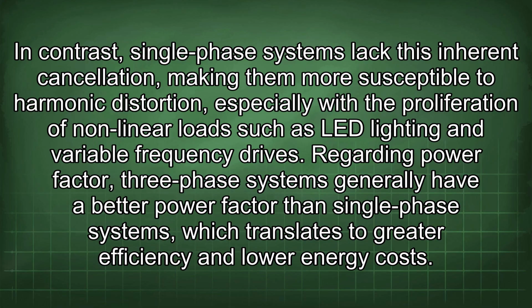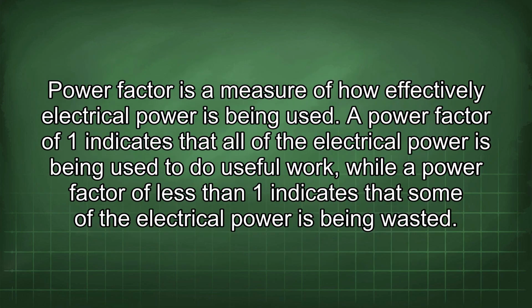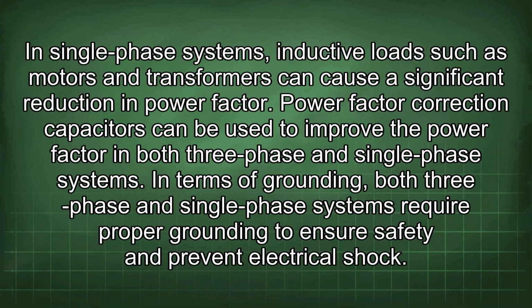Regarding power factor, three-phase systems generally have a better power factor than single-phase systems, which translates to greater efficiency and lower energy costs. Power factor is a measure of how effectively electrical power is being used. A power factor of 1 indicates that all of the electrical power is being used to do useful work, while a power factor of less than 1 indicates that some of the electrical power is being wasted. In single-phase systems, inductive loads such as motors and transformers can cause a significant reduction in power factor. Power factor correction capacitors can be used to improve the power factor in both three-phase and single-phase systems.